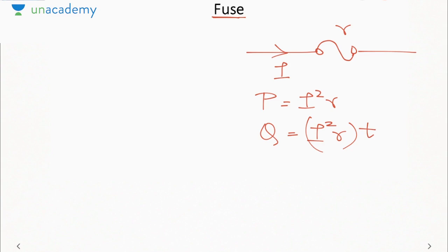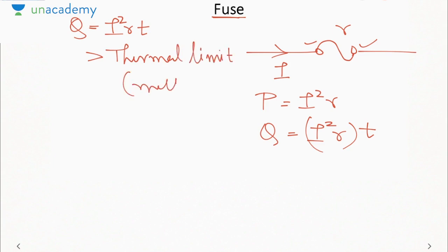Now, due to the heat being produced in the fuse, the temperature of fuse will keep on rising. As the temperature increases and it goes beyond the melting point of fuse, the fuse will melt down, and hence it will disconnect these 2 points from the system. Okay. So its principle is based on the amount of heat produced in the fuse. Now heat produced is I square R into T. This must be greater than thermal limit, so that the fuse will melt down. Thermal limit is the amount of heat required to melt the fuse. Okay. We usually understand the thermal limit in terms of melting point, but here we are understanding in terms of the energy that is required to melt the fuse. So whenever Q is greater than thermal limit, the fuse will operate.